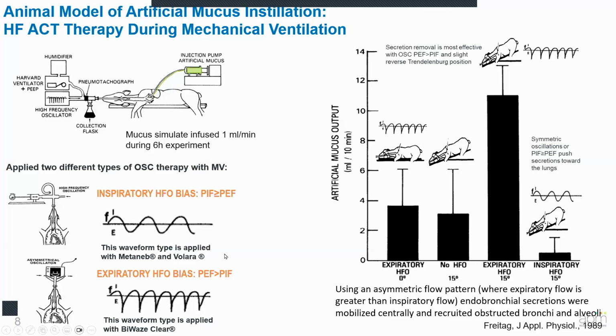And so a lot of the devices like the Metaneb and the Volara will apply high frequency oscillations like this, where either the inspiratory flow is greater than the expiratory flow. That would be the flow bias, where peak inspiratory flow is greater than peak expiratory flow, or it's equal, just like an oscillator. Now, what they also did is they looked at the device when they were able to manipulate the flow waveform to look more like a cough.